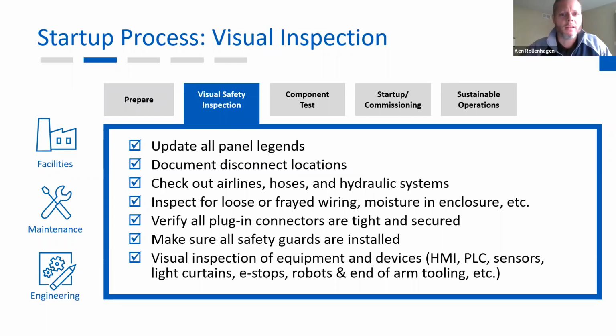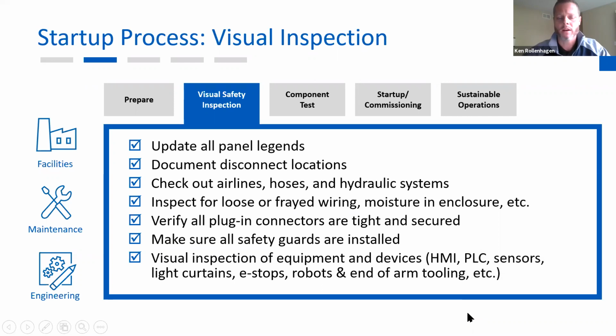So when it comes to that first visual safety inspection, when you're bringing things back online in that startup process, from a facilities standpoint, it's real easy just to do a walk through your building and your one line diagram, everything from the main coming in. You want to make sure that all of your panel legends are updated, any changes, making sure that those are documented. Document disconnect locations. Again, this pertains to that lockout tagout procedure. Where do I go to keep myself safe? It can eliminate a lot of time for maintenance personnel, in that direction and not figuring it out.